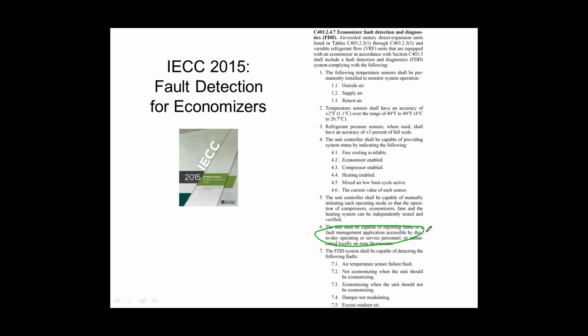So first thing is you're probably not going to be able to use any of the old economizer controllers that you used to use, right? Stuff that you were using for the past decade does not have the ability to monitor any of this stuff. Most manufacturers use Honeywell controls. Honeywell has one controller that does this. It's the Jade controller. By the way, Honeywell 2 years ago announced they are stopping manufacture of all economizer controllers, even for replacement part purposes, and they're only going to make one, which is this Jade controller.